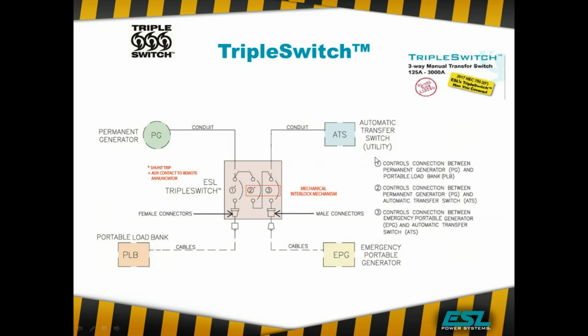We're sending that remote annunciator signal back to the facility to meet NEC 703F. And then you have your male cam locks for your portable generator, for if this is offline and you were to lose your utility power, now you can provide power directly to the facility with the portable generator. In these applications, the triple switch also comes with the terminal block for the remote auto stop and start signal for the portable generator. So it now acts just like the permanent generator.